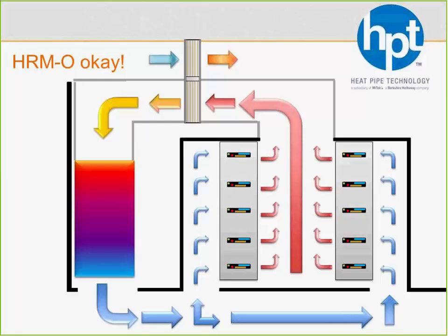And you can actually use our HRMO, the over-under, because again, with a data center, you're only concerned about pre-cooling that air and whisking away that heat. So if you wanted to put the fan unit or the outside portion on the roof, that's perfectly fine because all you're doing is pre-cooling anyway. So whether you're putting it on the sidewall or on the roof, it's going to do the same thing for you.